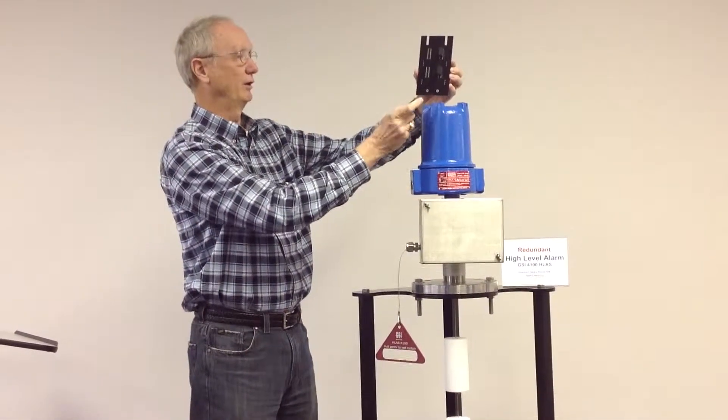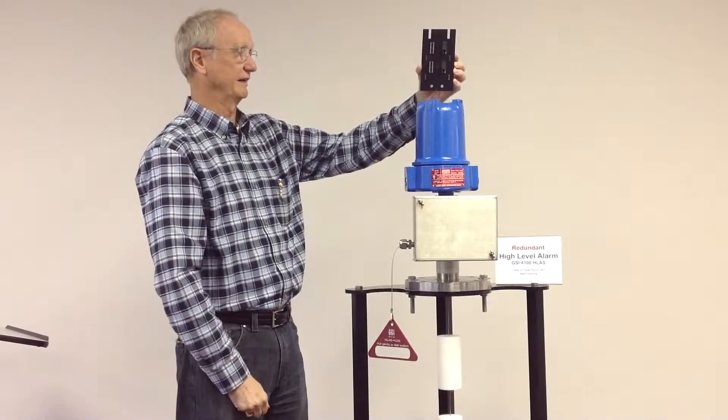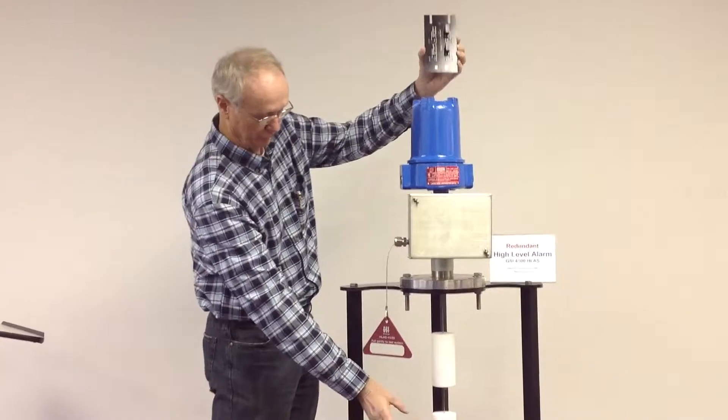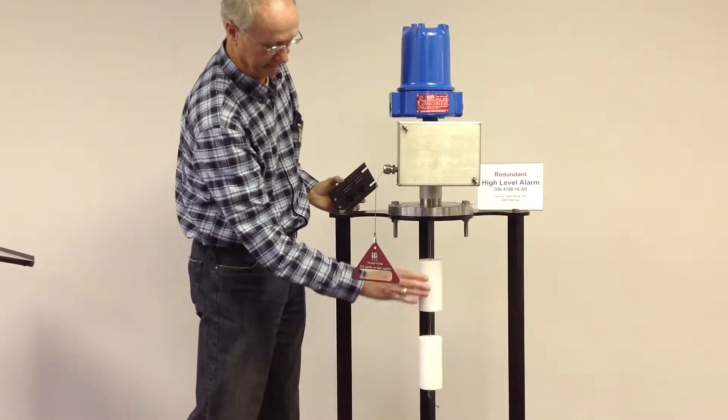When you have reed switches in each of the four sockets, you have a totally redundant switch for two displacers - one for high and one for high-high.